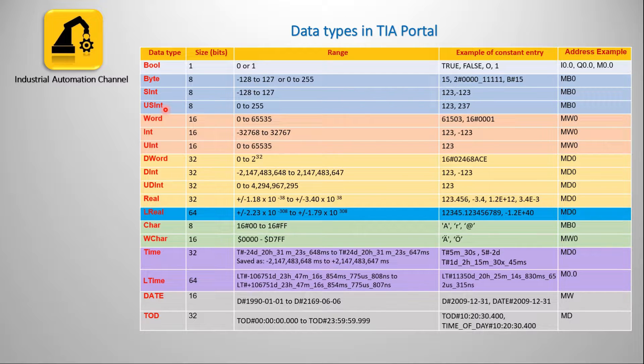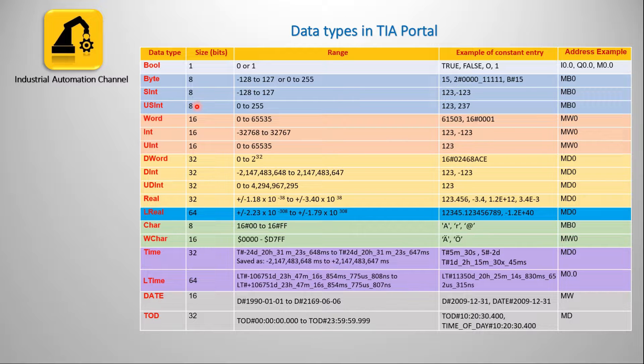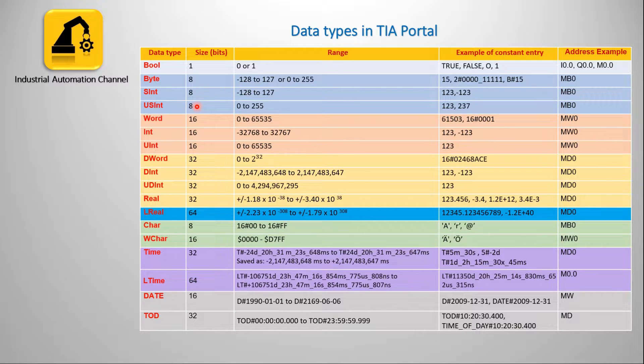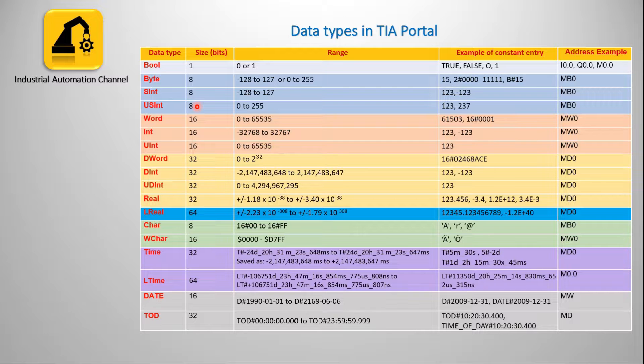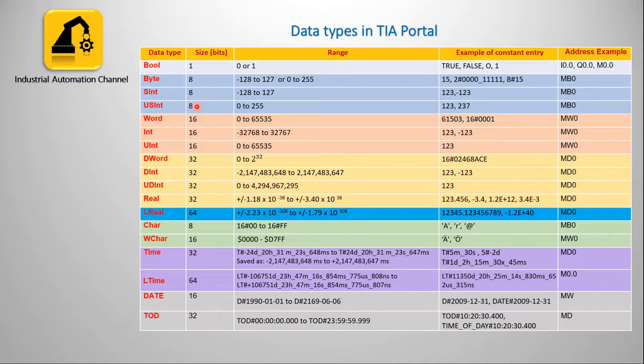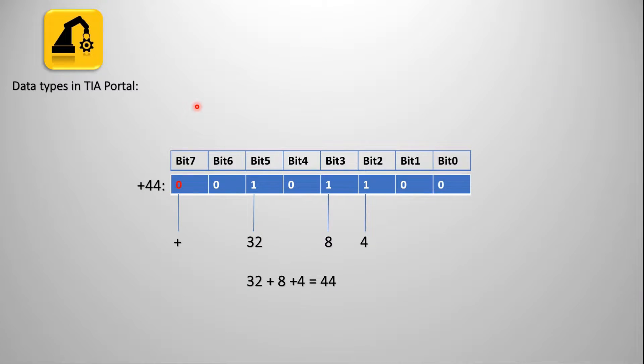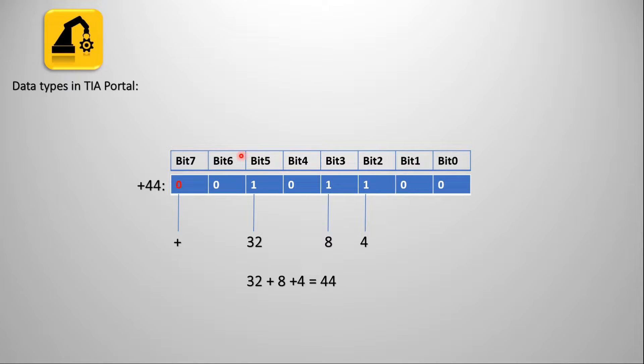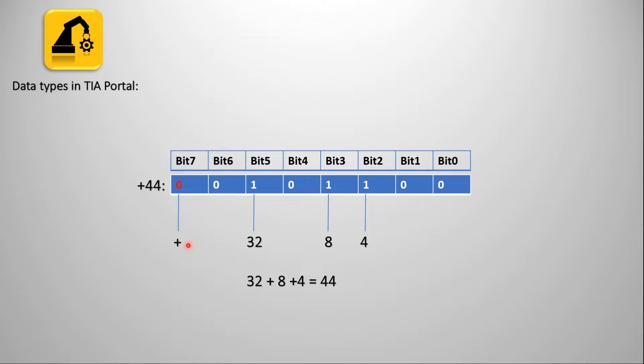Short integer and unsigned short integer are similar to bytes. They have also a length of 8 bits and both are represented by MB. In other words, an operand of data types short integer or unsigned short integer occupies one byte in the memory. Short integer consists of two components: a sign and a numerical value. The signal states of bits 0 to 6 represent the number value, and the signal state of bit 7 represents the sign: 0 for the positive and 1 for the negative signal state. For example, the following figure shows the integer value for plus 44.